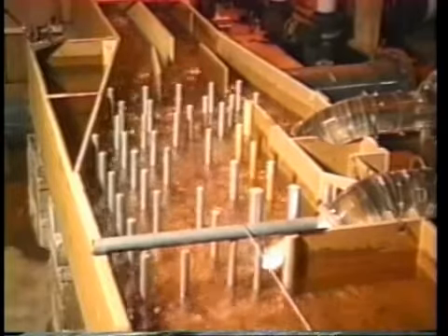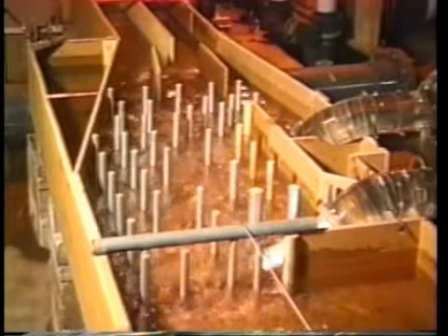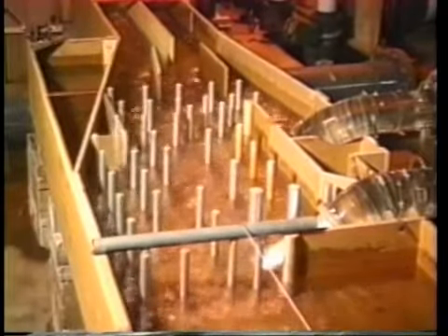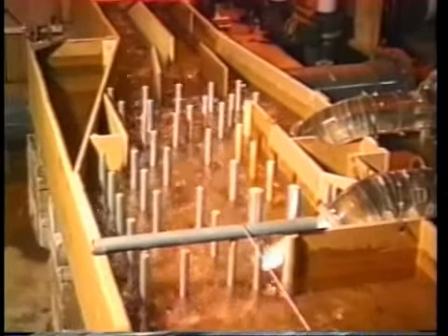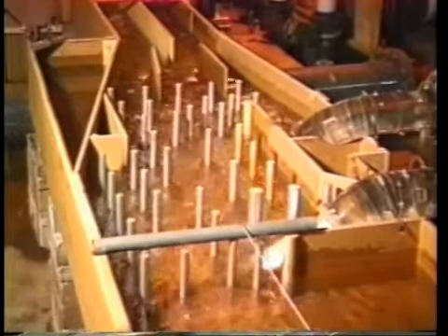We went in and modeled every station that we made an improvement on. And we found out that the theory back at the turn of the century was, if you want to pump more water, you put in more pumps. Well, that's not necessarily efficient, because some of the pumps were fighting each other. By making an authentic model of the station, we were able to find things like vortices being developed on the floors of the stations, and by merely putting in small walls in some of the stations, we've been able to improve the stations by 1 or 2 pumps sometimes. Right now, this station is so efficient, the canal that supplies it is inadequate. We have to more than double the size of the canal coming into the station to get the water to the station.